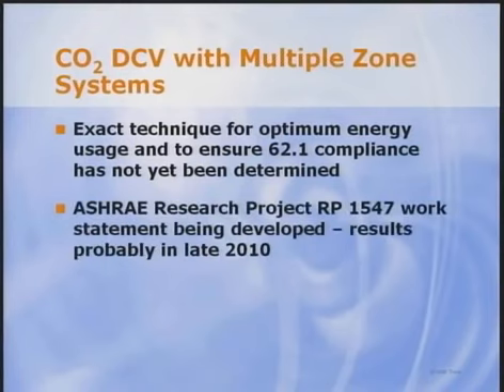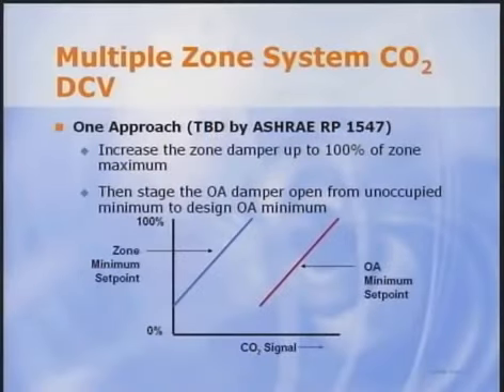The only time the DCV logic will really come into play is when the air handler is on minimum outdoor air, either because it's very cold or very hot outside. Under these conditions, it is logical that increasing reheat at the zone level will have a smaller energy impact than increasing minimum outdoor air rates at the air handler and overventilating the whole building. Hence, the sequence first tries to ventilate the DCV zones with more supply air, essentially transfer air from overventilated zones, and then calls for additional outdoor air at the air handler. We'll see if ASHRAE's research project corroborates the efficiency of this sequence or finds another to be more effective.